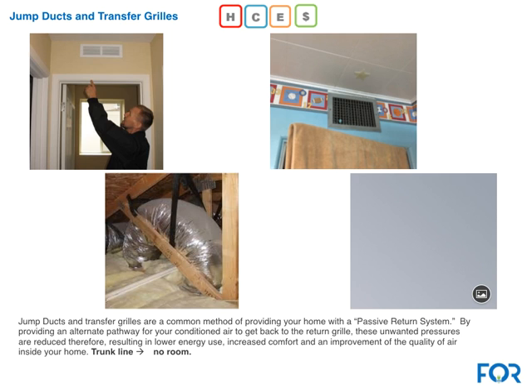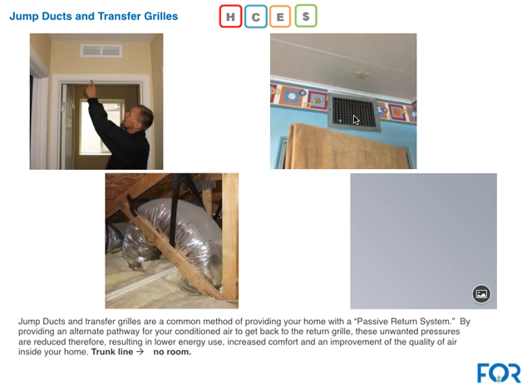In a home with trunk lines, registers stick out of the wall. Remove the screws, pull the grill off, and you'll be able to photograph a couple of things: the gap between the actual duct and the sheetrock around the edge, and by sticking your phone inside, you can photograph the seams and see where air drops from the attic into the trunk line and how the flanges aren't properly sealed. Pull two or three registers and get high-quality pictures for the duct page.